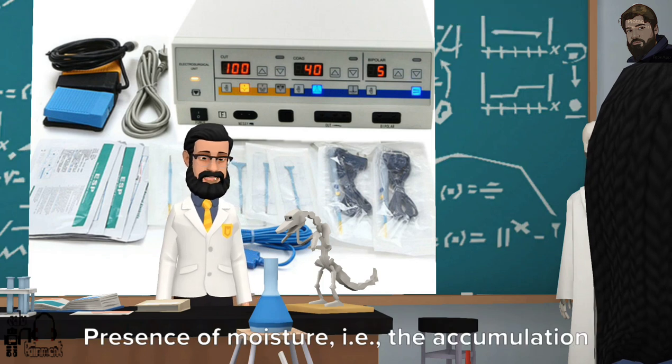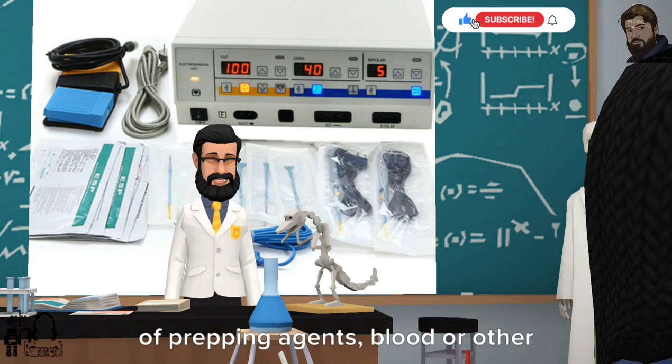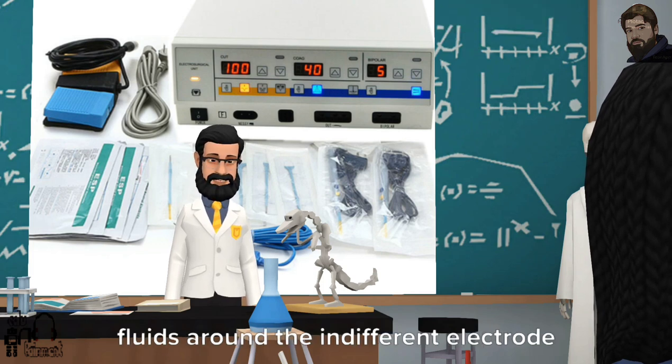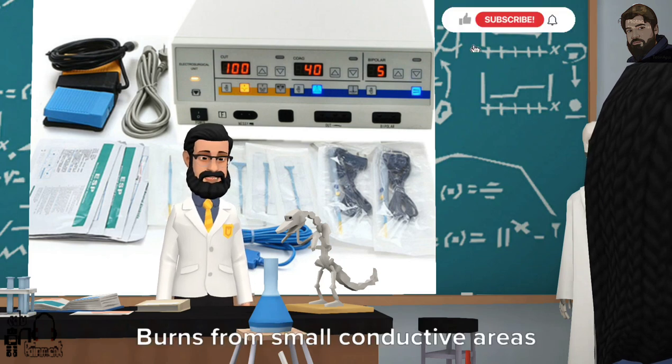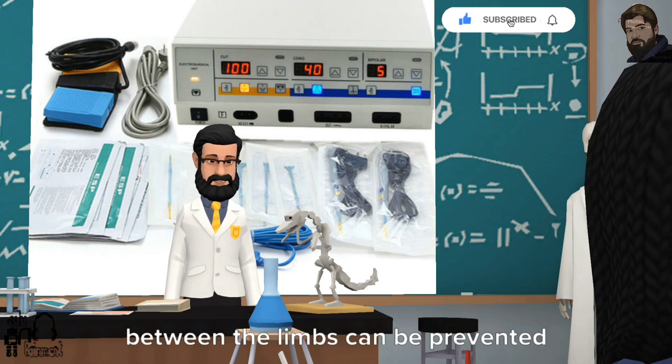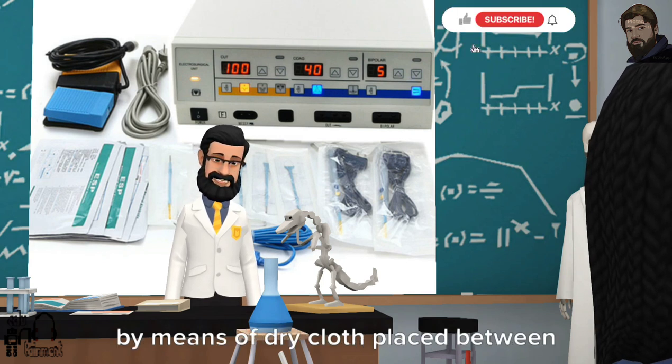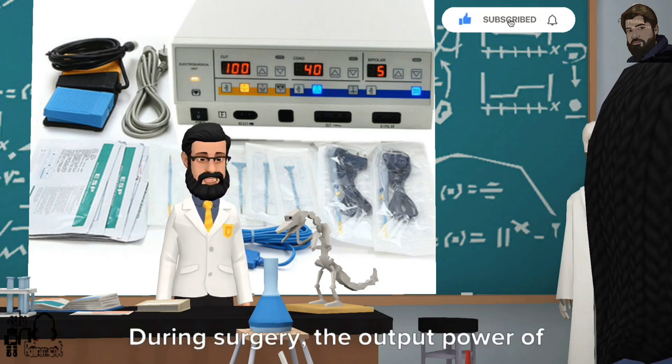6. Presence of moisture, that is, the accumulation of prepping agents, blood or other fluids around the indifferent electrode can give rise to small, highly conductive areas. Burns from small conductive areas between the limbs can be prevented by means of dry cloth placed between them.